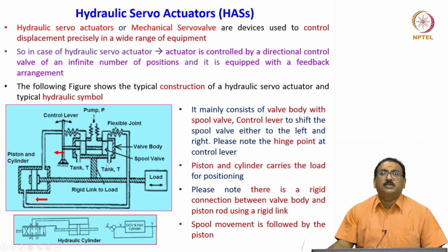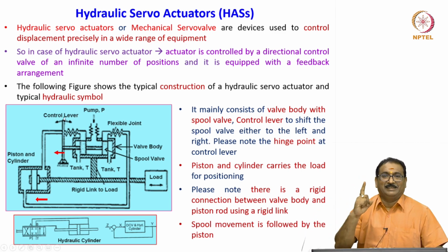Please remember, friends, the piston follows the spool motion. Both will move in the same direction. As it moves, what happens? You will see here, it is moving, no? The whole body is also moving. Meaning this lever, whatever you moved, it will bring back to the null position. Feedback is there. That's why I am telling. Please understand this very carefully.